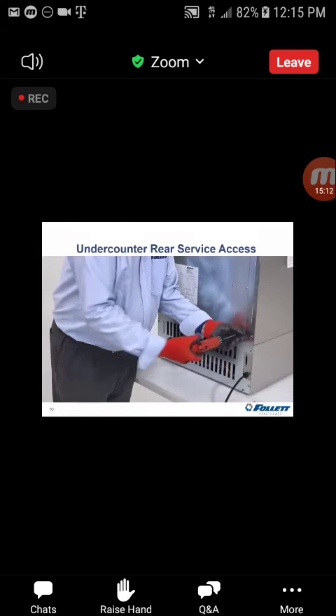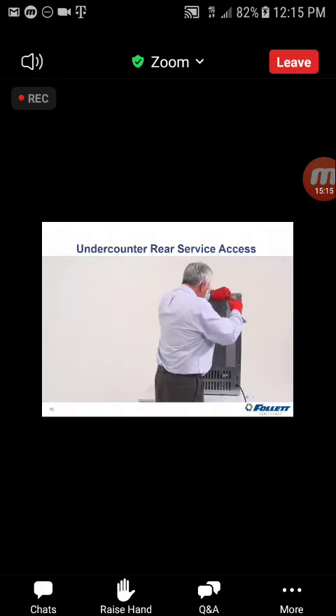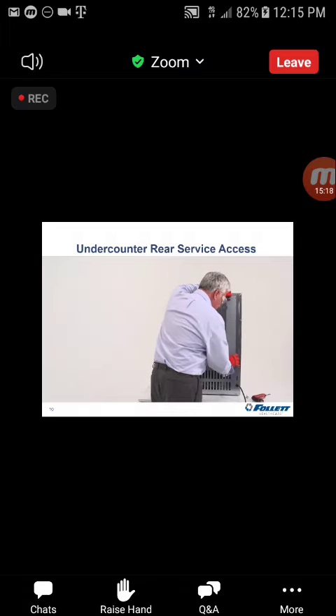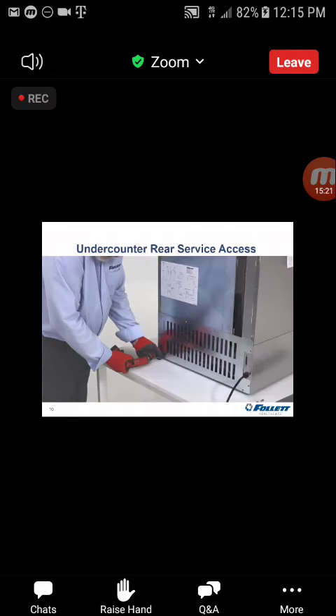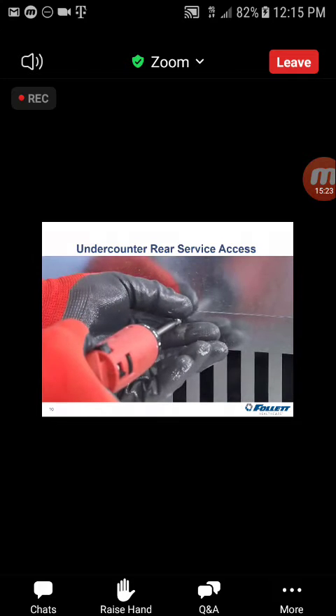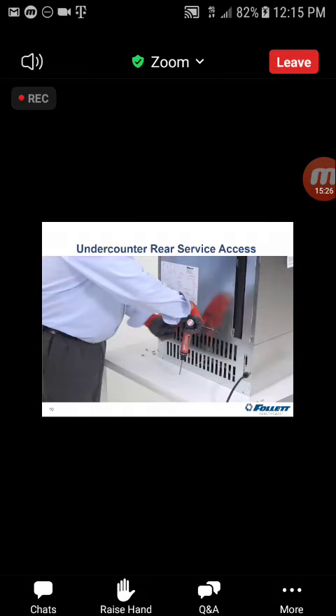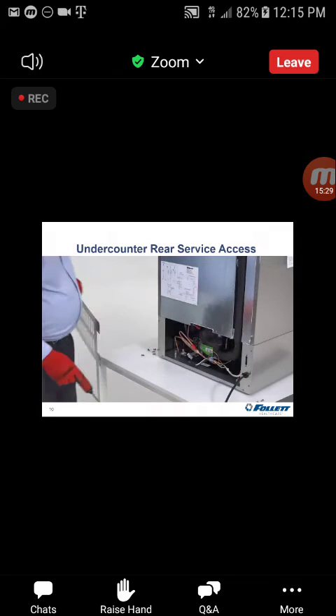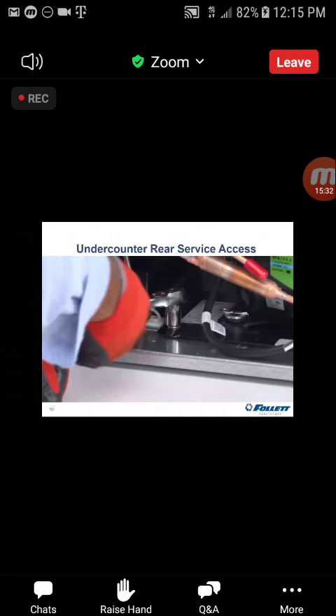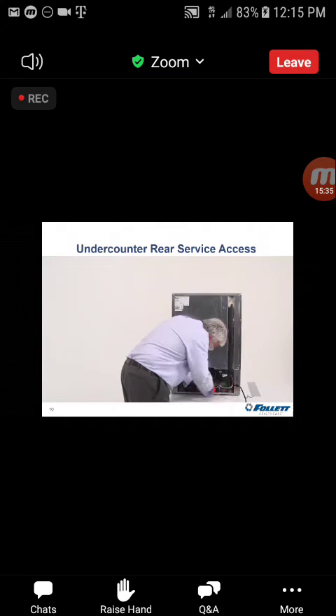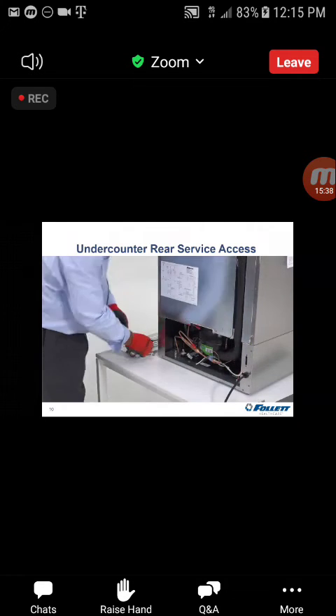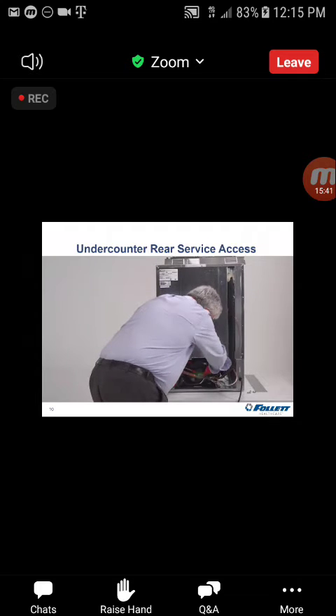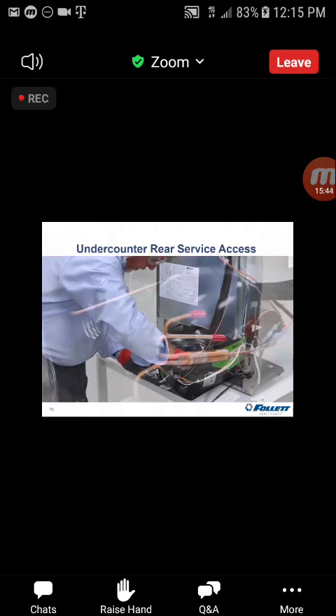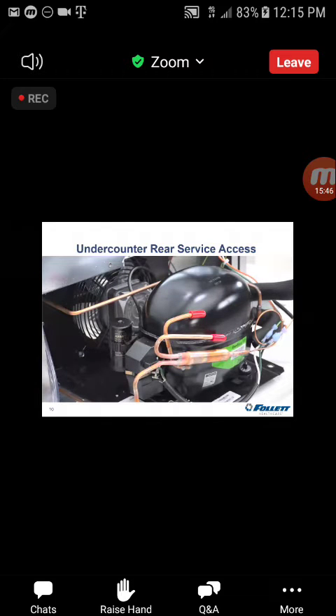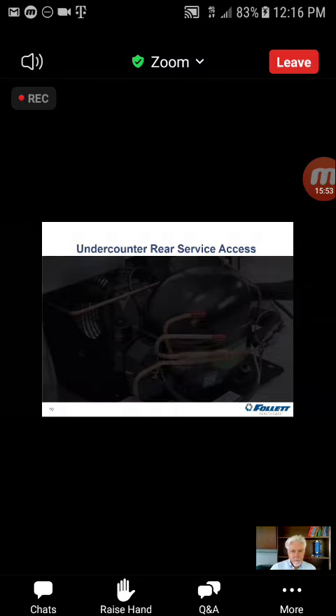Once you have removed the baffle, then from the back of the unit, remove both service panels, the one covering the refrigeration tubing and the access panel at the bottom. Once the panels are removed, remove the two 1/2 inch bolts that secure the condensing unit to the base. The unit can now be partially withdrawn, giving you access to the condenser fan motor, the condenser fan blade, the compressor, and the compressor starting components.